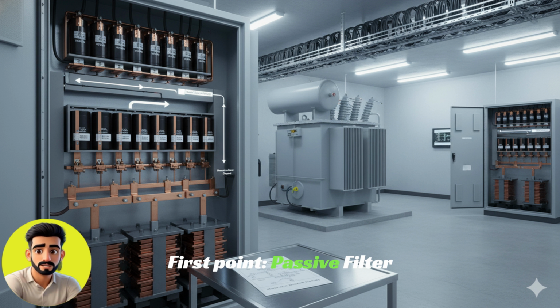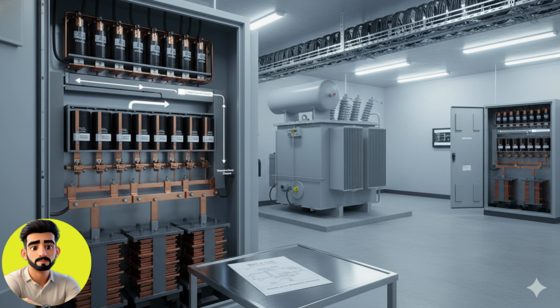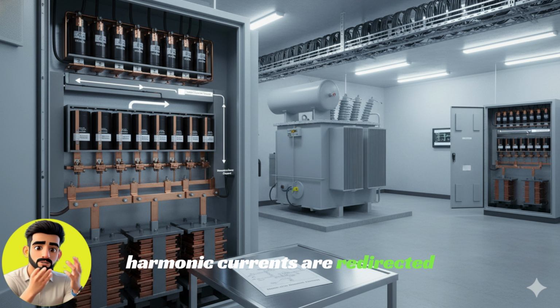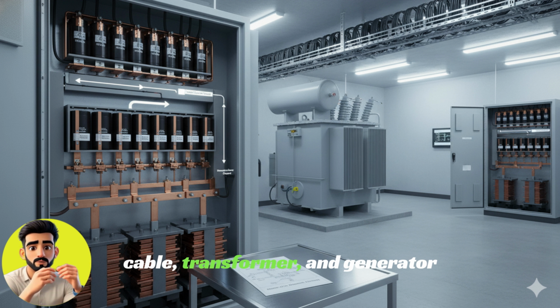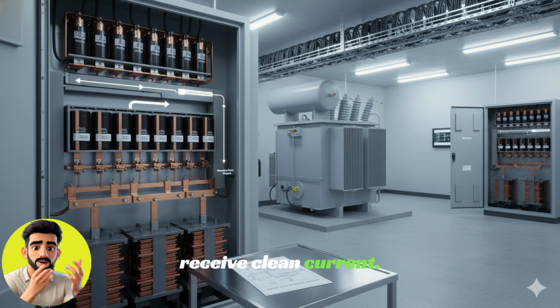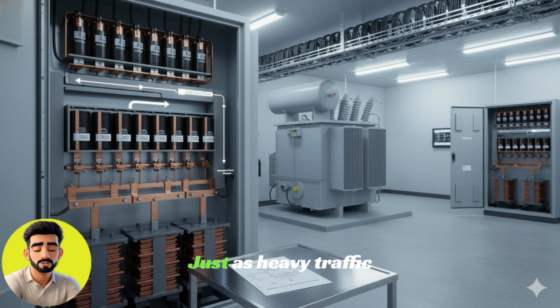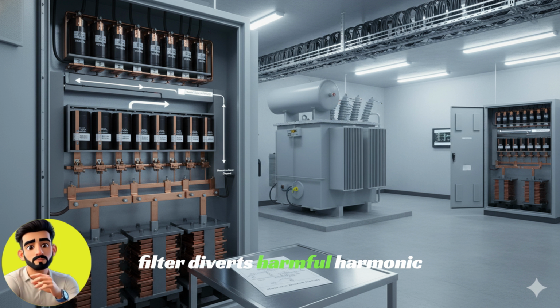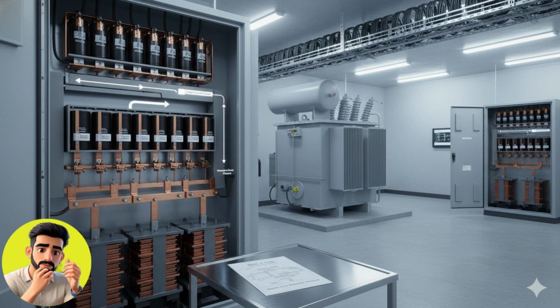First point, passive filter only absorbs harmonics. It does not affect the main frequency. This filter acts as a side lane where harmonic currents are redirected so that the main cable, transformer, and generator receive clean current. Understand this with a simple example. Just as heavy traffic on the road is diverted to a bypass road, similarly, a passive filter diverts harmful harmonic currents. The second point is that a passive filter is tuned for a specific harmonic.